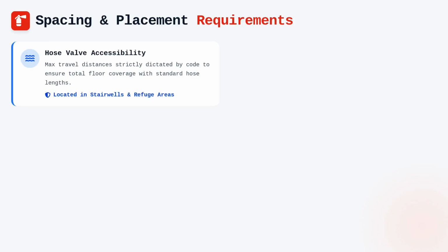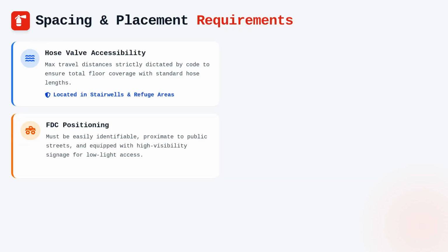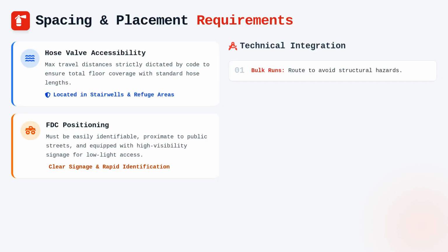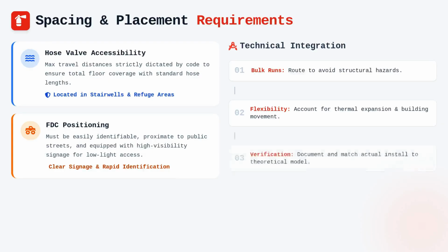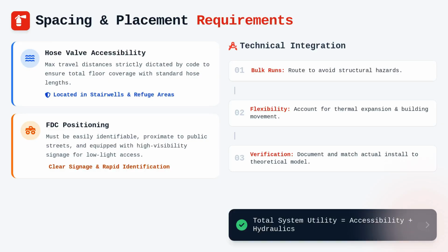These valves must be located in protected stairwells or designated areas of refuge to ensure they remain accessible even during an active fire situation. Furthermore, the fire department connection, or FDC, must be positioned where it is easily identifiable and accessible to the responding fire department, often requiring proximity to a public street and clear signage that remains visible even in low light conditions. The integration of these components requires a meticulous approach to bulk runs, as the piping must be routed to avoid structural hazards while maintaining enough flexibility to withstand thermal expansion and building movement. Every piping segment must be documented and verified to ensure that the actual installation matches your theoretical model.